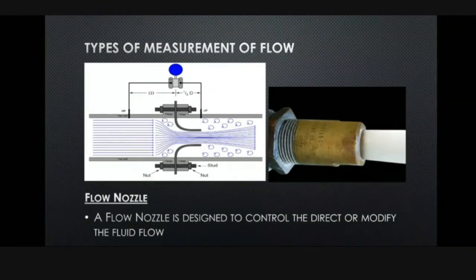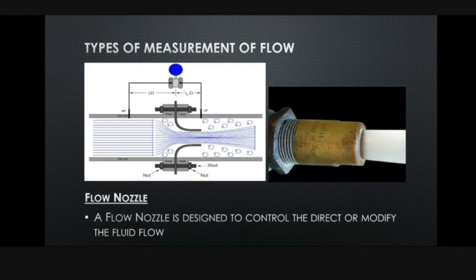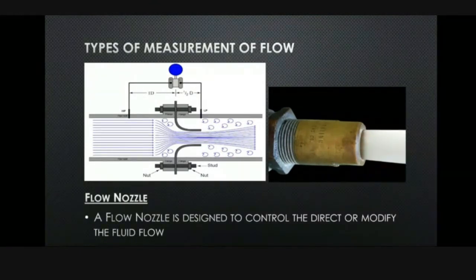A fluid whose flow rate is to be measured enters the nozzle smoothly to the section called the throat, where the area is minimum. Before entering the nozzle, the fluid pressure in the pipe is P1. As the fluid enters the nozzle, the fluid converges and due to this, its pressure keeps on reducing until it reaches the minimum cross-sectional area or throat. This minimum pressure P2 at the throat of the nozzle is maintained in the fluid for a small length after being discharged in the downstream also. The differential pressure sensor attached between points 1 and 2 records the pressure difference P1 minus P2 between these two points, which becomes an indication of the flow rate of the fluid through the pipe when calibrated.